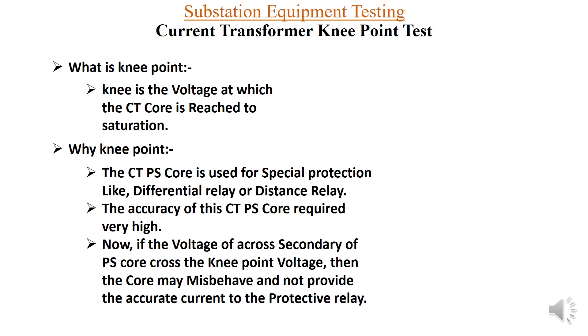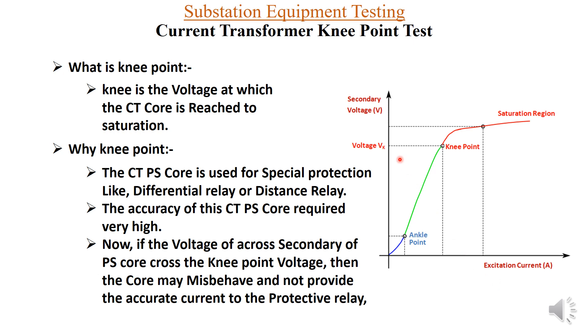The graph shows secondary voltage versus excitation current. As you can see, this kind of graph is obtained, and this point is called the knee point, with the voltage here called the knee point voltage. Beyond this, if the voltage is increased, the excitation current increases very fast and becomes very high. This region is called the saturation region, and the high excitation current can damage the core of the CT.